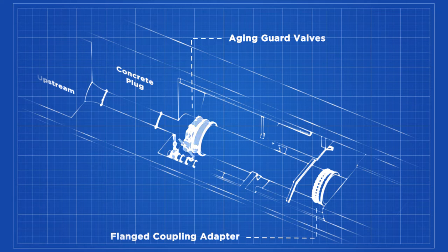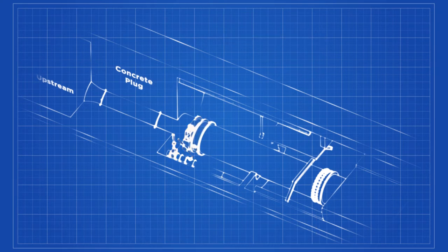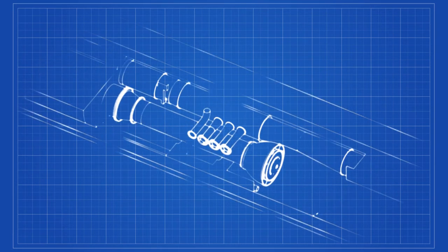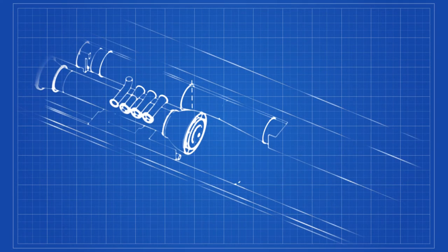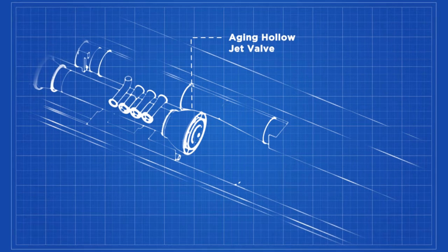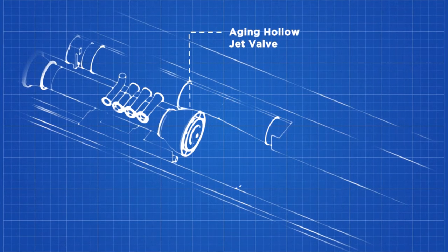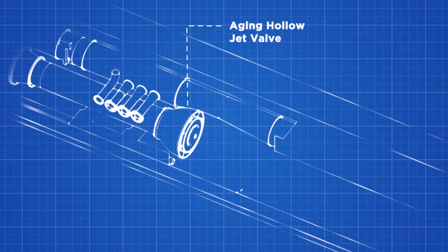These valves were installed during the construction of the dam around 1950 and were designed to last 50 years. Approaching 70 years of service, the valves had deteriorated and were leaking heavily. Downstream of the 72-inch guard valve connects to a hollow jet valve, which dissipates energy and controls the water flow rate through the tunnel. This hollow jet valve was also installed in the 1950s and also leaked heavily.